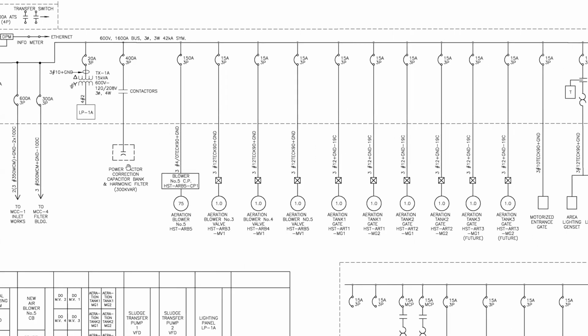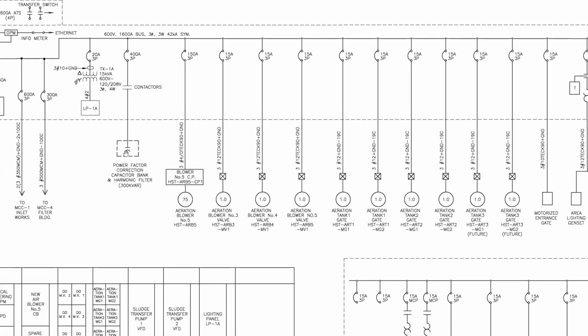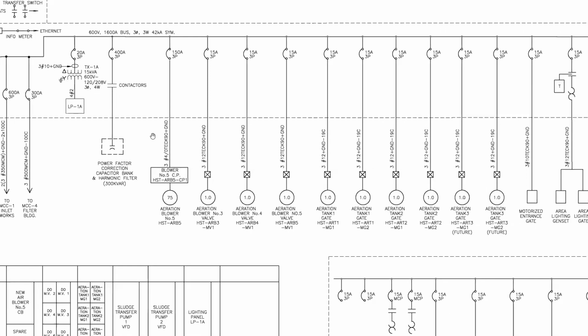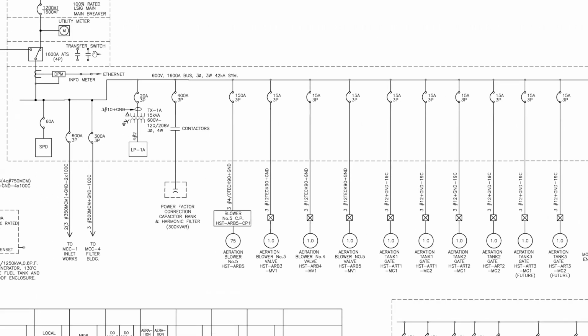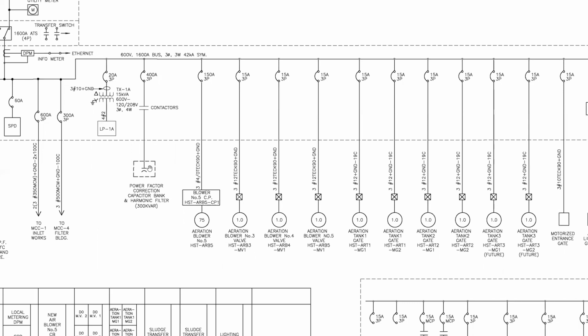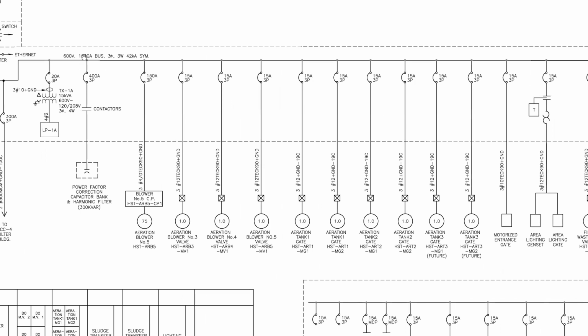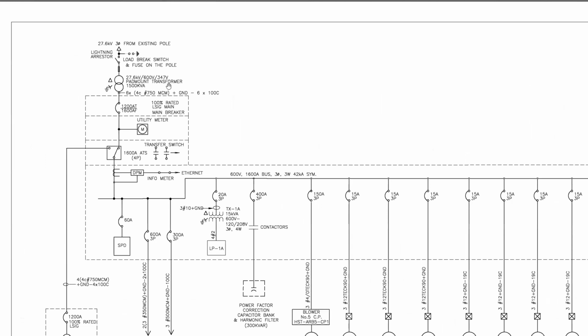600 or 400 amp here is going to connect to a contactor, and then to a power factor correction capacitor bank. So you can see here that capacitor symbol that I was showing you before. If you get into more electrical theory, you'll have leading and lagging, and a power factor of a device. When you get to a certain size, you'll have a power factor of an entire facility. This power monitor will monitor the power factor of the facility, and it will turn on and off different capacitors to adjust it.